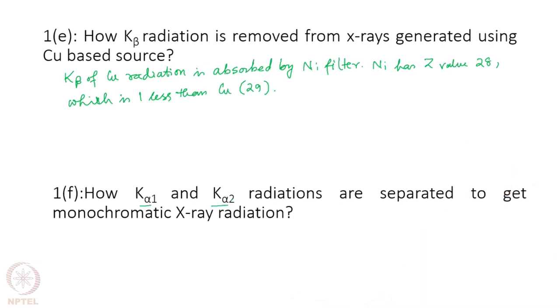How are K alpha 1 and K alpha 2 radiations separated to get monochromatic X-ray radiation? This separation is difficult and it also involves a loss of intensity of both alpha 1 and alpha 2, and it is done by using a monochromator which is actually a crystal of germanium. So, what is done is a crystal of germanium is cut along the 111 plane, which you may not understand right now. At the moment take it as the Miller indices of that particular plane, which I will explain later.